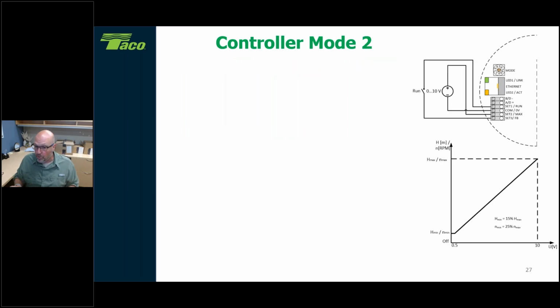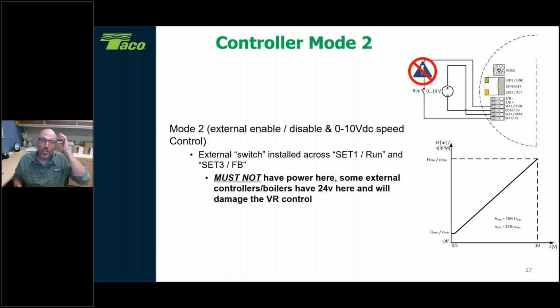In mode 2, since we have a minimum speed that we're going to make the circulator run at, now we have a second external switch coming in, an end switch, to tell it to turn on. So you've got 2 things happening here. You have 0 to 10 and an end switch coming in. And this is going to take that dial and put it into mode 2. So now we have our external enable.